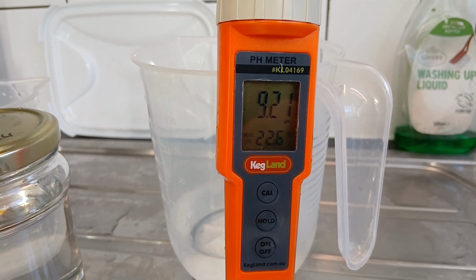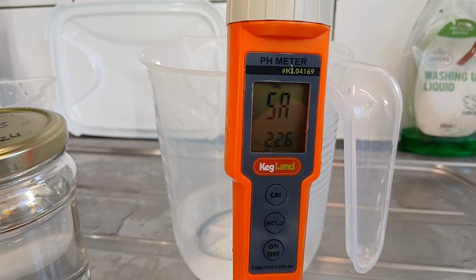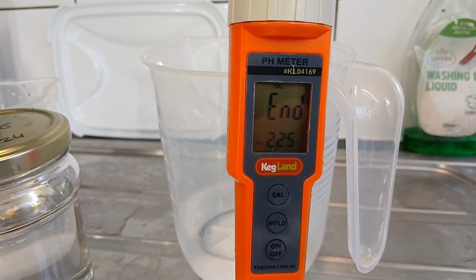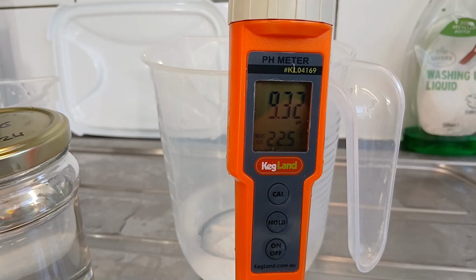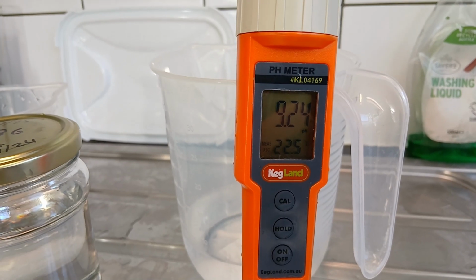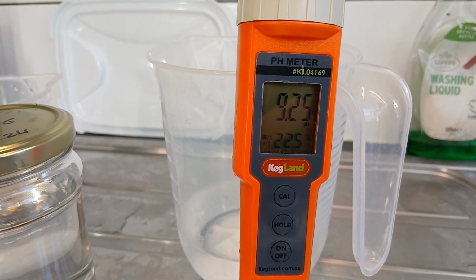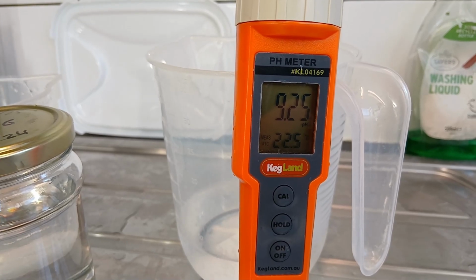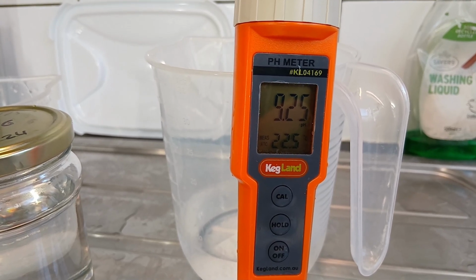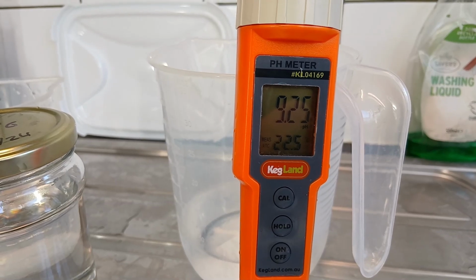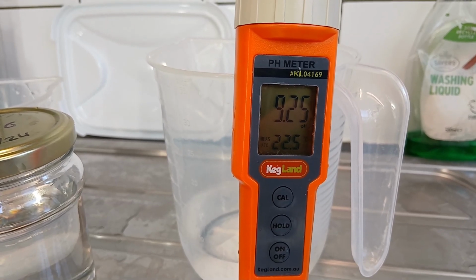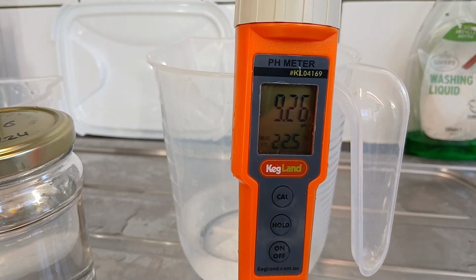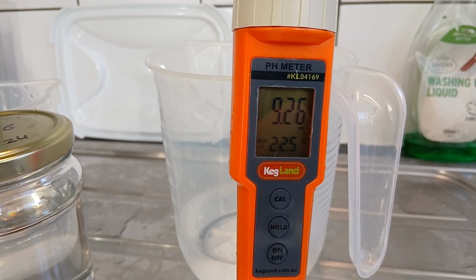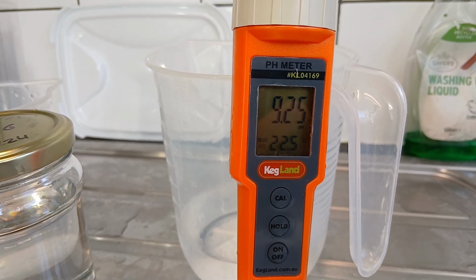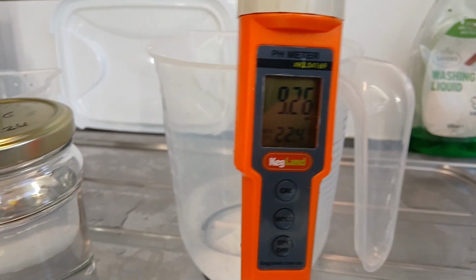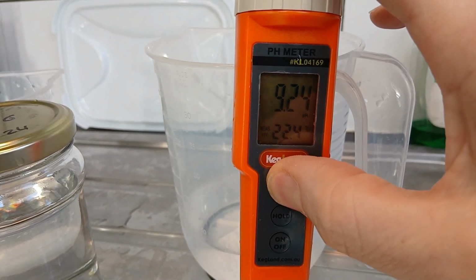I think what I'm going to do after we've finished this calibration, I am going to recheck it down at the level of a 4, probably the 4 and the 6.86 again, just to check that it is still holding down the lower end where it's more important. That's still a little high. Let's run that through the cal again.